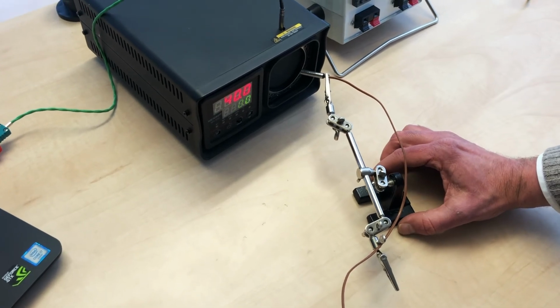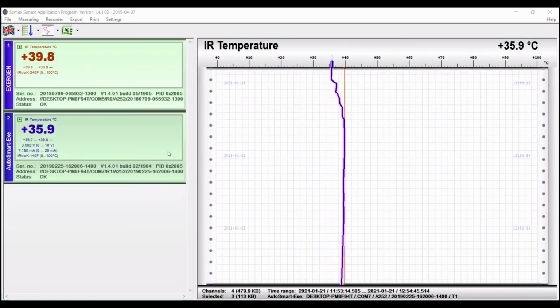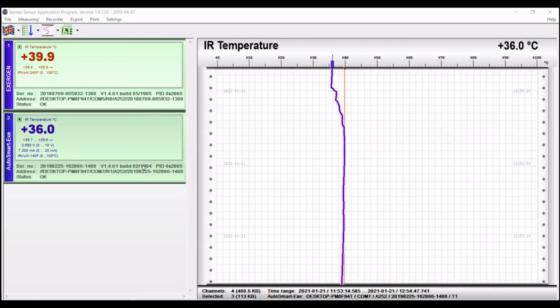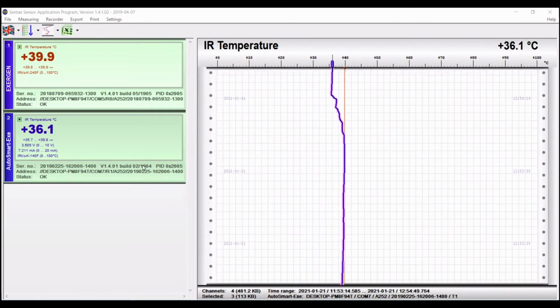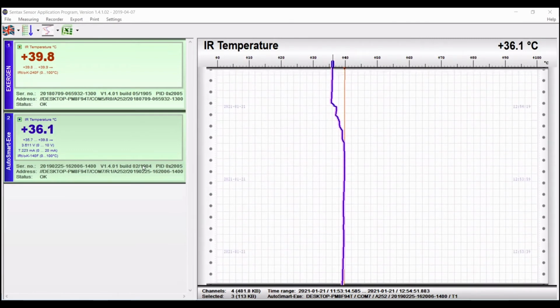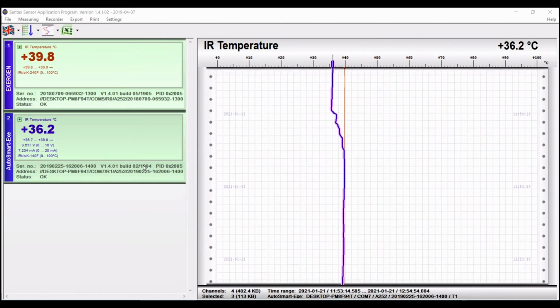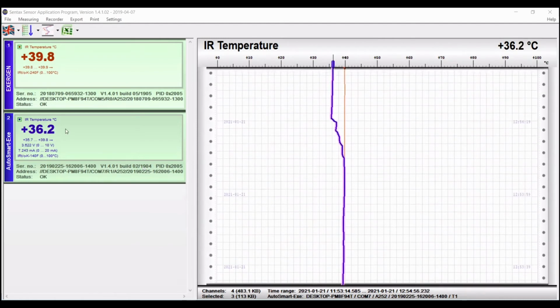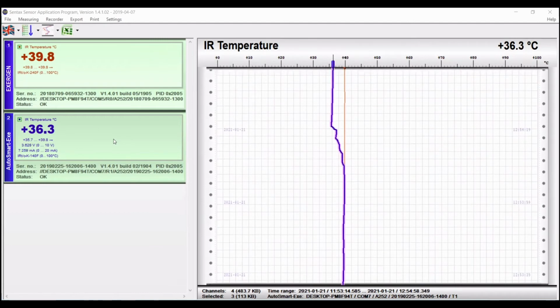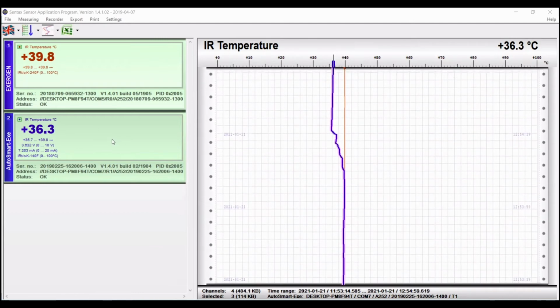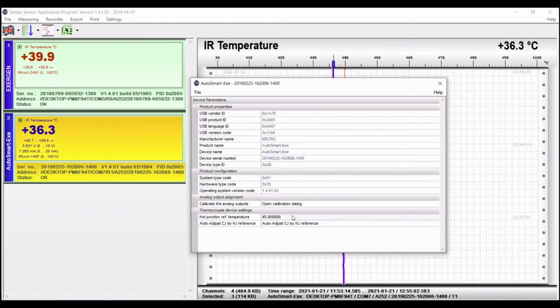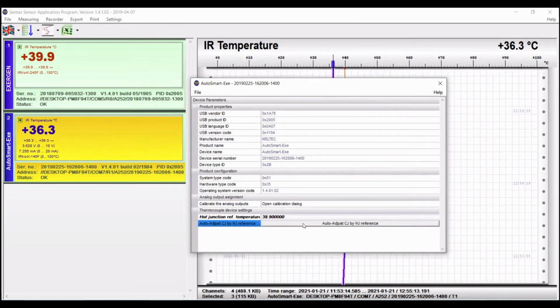Now you immediately see an effect in the reading, where the sensor now, because of field of view issues, is giving a different reading than the target and the blackbody, because there are other things in the field of view that affect the reading. But I can adjust for this. Let me show you how that works. So here on the software, I click. Now my reference sensor is 39.9. I put in the 39.9 value here in the software, and then I press Auto Adjust.